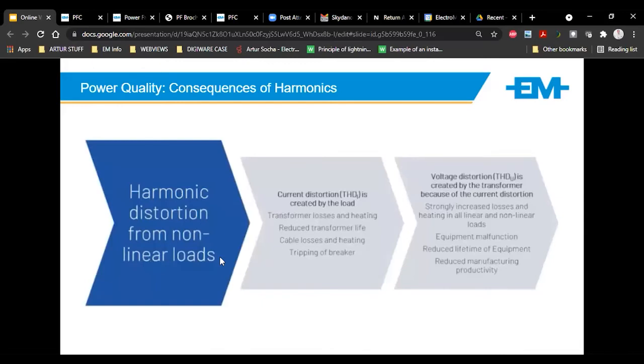So current harmonic is created by the load, and causes transformer losses, reduced transformer and cable life, and tripping of breakers. This is obviously depending on how high this current harmonic is. And that results in a voltage distortion at the transformer. This is also an important part to take here: it depends how loaded the transformer is. What capacity is it at? If it's at 100% capacity and you've got all these switch mode supplies downstream, it creates additional stress onto the transformer.